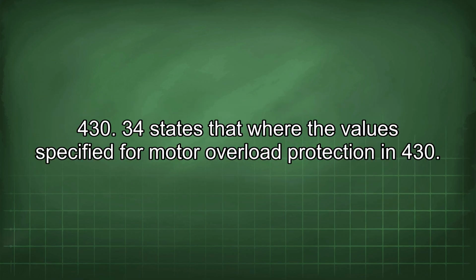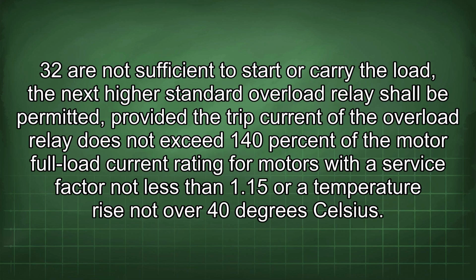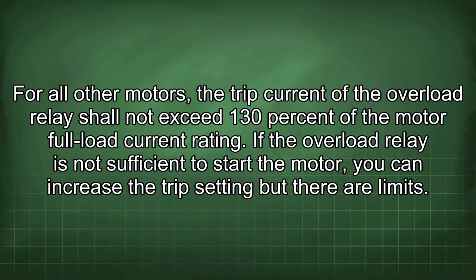430.34 states that where the values specified for motor overload protection in 430.32 are not sufficient to start or carry the load, the next highest standard overload relay shall be permitted, provided the trip current of the overload relay does not exceed 140% of the motor full load current rating for motors with a service factor not less than 1.15 or a temperature rise not over 40 degrees Celsius. For all other motors, the trip current of the overload relay shall not exceed 130% of the motor full load current rating.